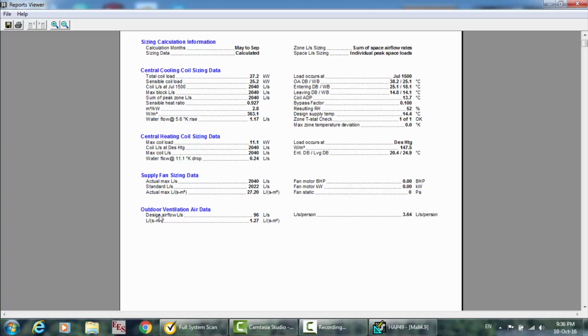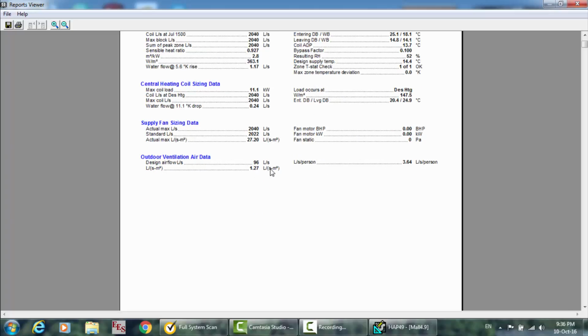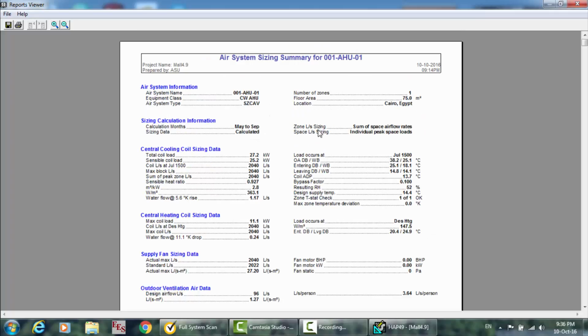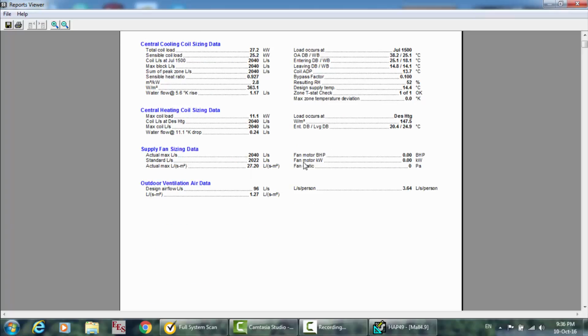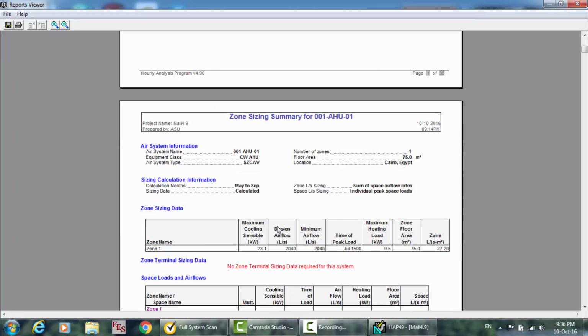And here the outdoor ventilation air data is the design airflow liter per second is 96 liter per second. And this is for the full system, the old system. This is the amount you need for this zone, for the 3 spaces. Here is zone sizing and space, sum of space airflow rates, and individual peak space loads. So this is the total. And here the liter per second per square meter is 1.27, and liter per second per person 3.64 liter per second per person. And notice that it is page 1 of 35.